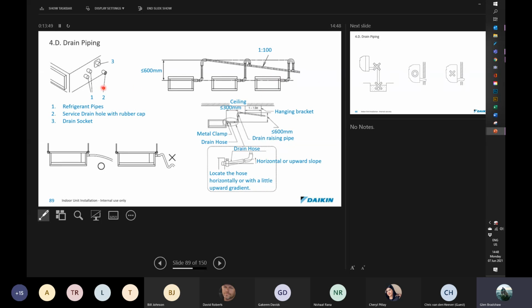It's also important to note where the refrigerant drains need to be. If there's a pump available, make sure that you've got it in the right place. If there is no pump, don't put your drain pipe at the top. You've got the unit upside down.